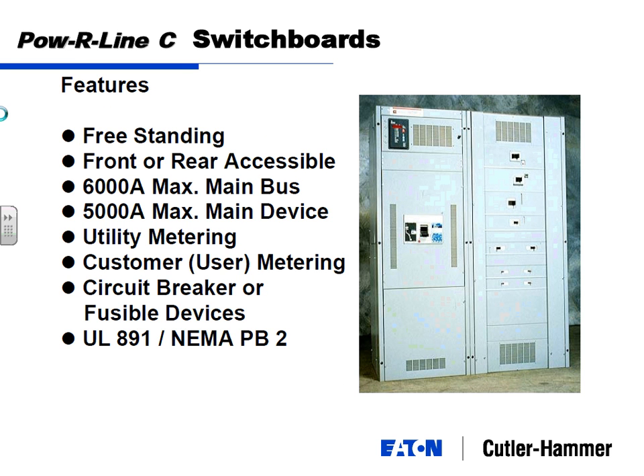Some of the other, sorry. Are all horizontal bus though? For switchgear? And I'm going to circle back to that, switchboards, because there is a difference between switchboards and switchgear. If they are all horizontal, 90% of the time, 95%. They all have that capability, but in the instance where you're above the 1200 amp, so maybe you've got 1600 amp, and all you want is one breaker, cable in, cable out, one breaker, you don't need the horizontal bus because you can fit everything you want in one structure. So there are instances where you build a switchboard and you don't need the horizontal bus, but most of them do.